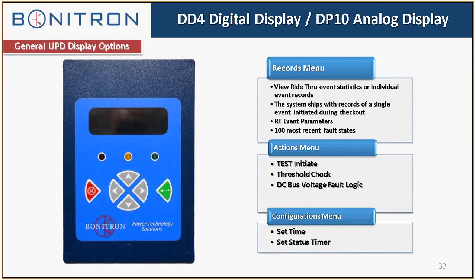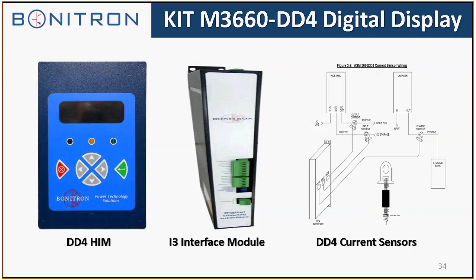And also it will monitor DC bus voltage fault logic. So in other words, it will let you look at the parameters of the AC line, DC bus, all the different parameters around the ride-through. And then there's timer settings also. So you can set the time to be able to know exactly when the ride-through event happened, and status timer also. In the kit, these units, the DD4 display, can be ordered in a module kit.